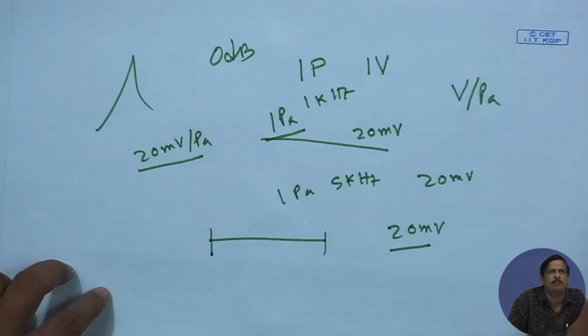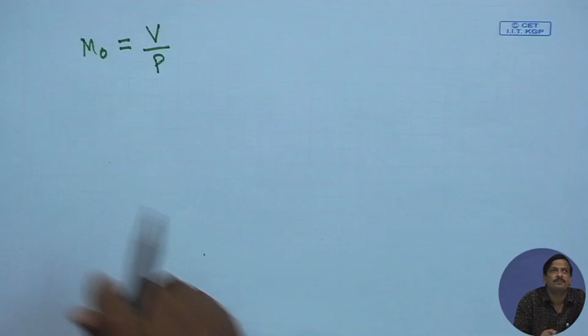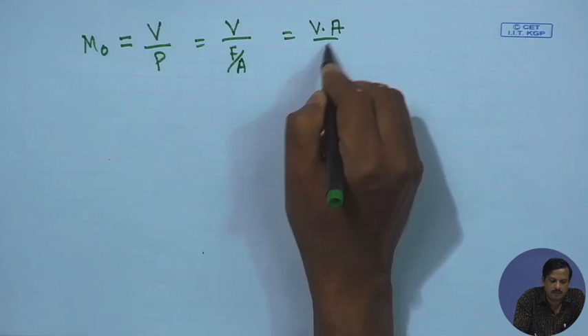So, let the sensitivity of the microphone be defined as M0. M0 is nothing but voltage per pressure. What is pressure? Pressure is nothing but force per unit area, so pressure is F by A. So, it is nothing but V into A by F, where V is the open circuit output voltage. The sensitivity is measured under the condition that the microphone is in open circuit. That means the microphone is not connected to another device; no load is applied to the microphone.